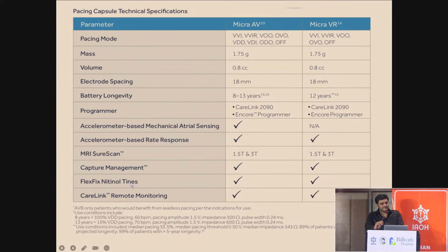as a single chamber. The mass and the weight of the Micra device is almost the same, and the volume is also 0.8. Since it is a dual chamber, the electrode spacing is 18 mm. The battery longevity is almost 10 to 12 years in both, and they have a similar programmer in both. As already said, it works mainly by accelerometer based rate response, it is MRI compatible, and capture management can also be done through remote monitoring. And in both systems, it is the nitinol tines which are used for anchoring in the RV.